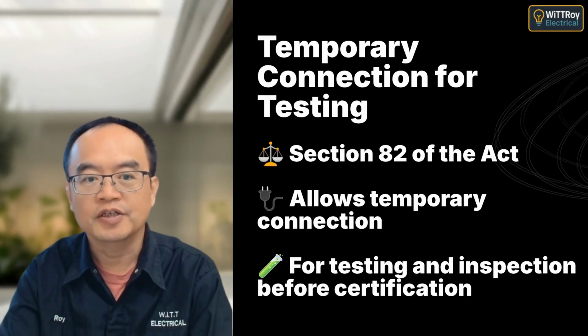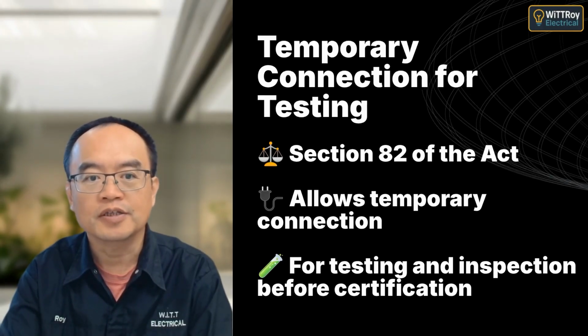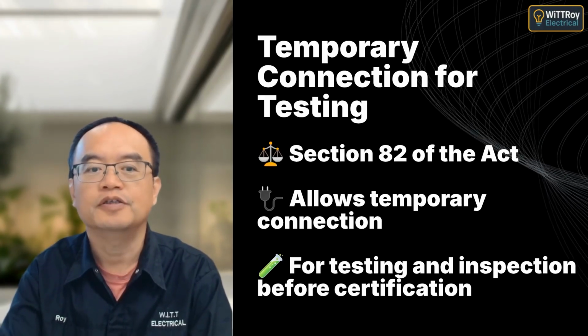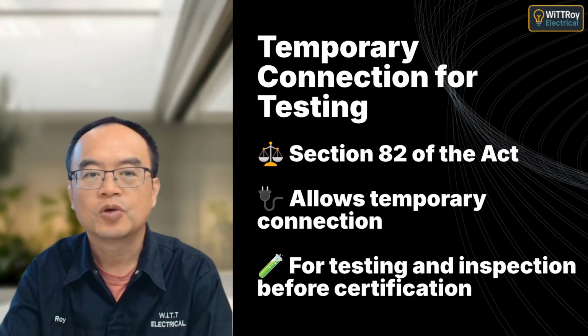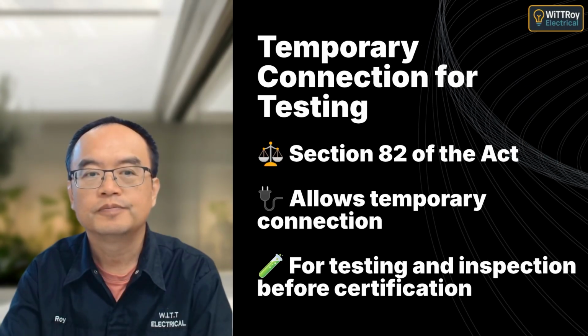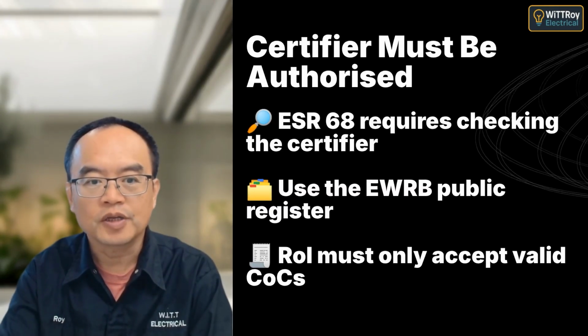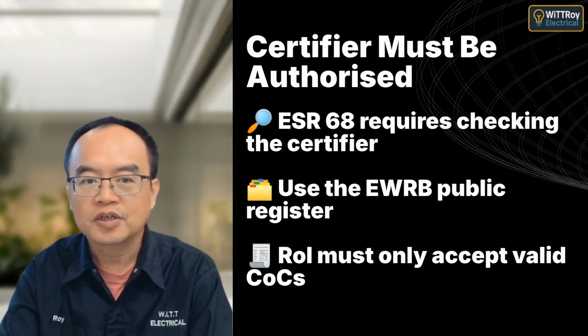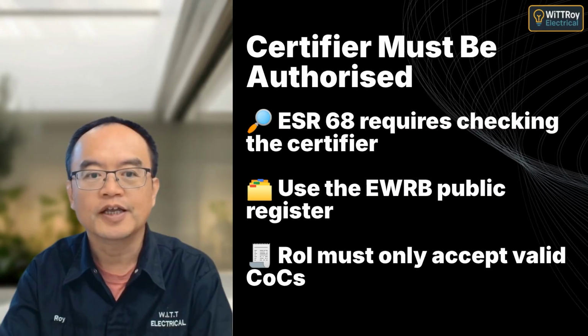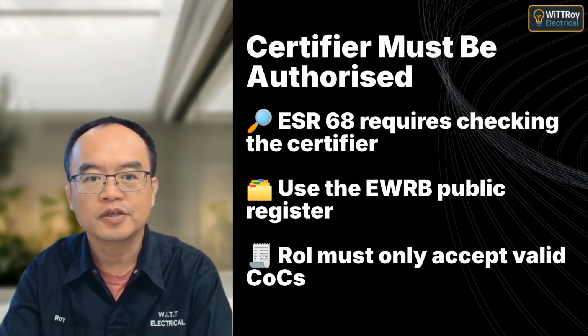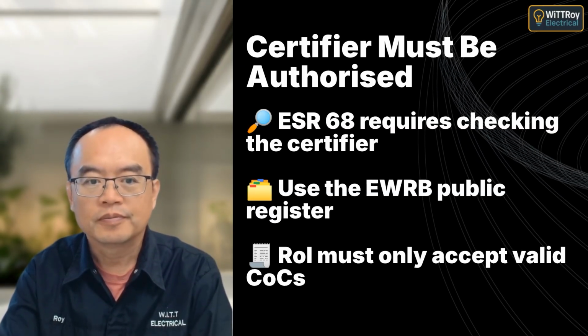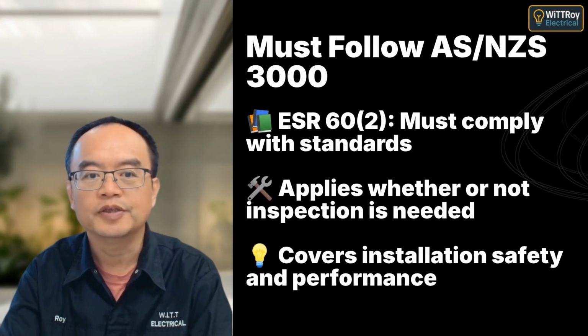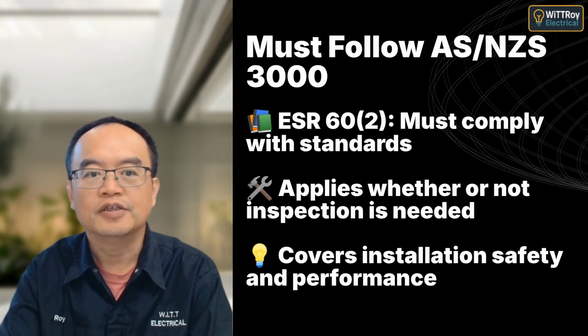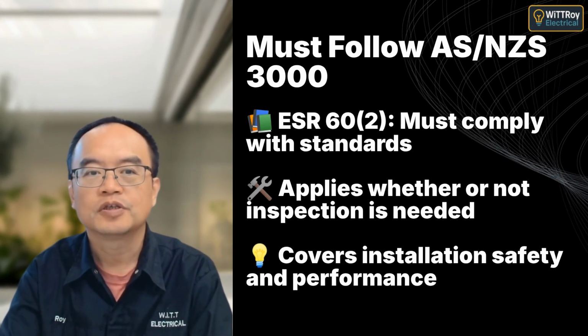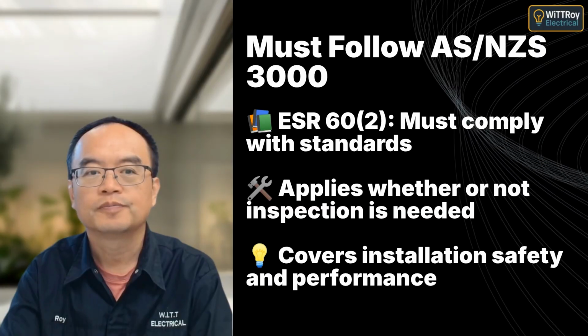Section 82 of the Electricity Act lets you connect the supply temporarily for testing and inspection. This helps confirm safety before you issue full certification. Inspectors must confirm that the person who issued the COC is authorized. You can check their current license using the public register. All work must meet AS/NZS 3000 and other cited standards, inspection or not. Compliance is always required.